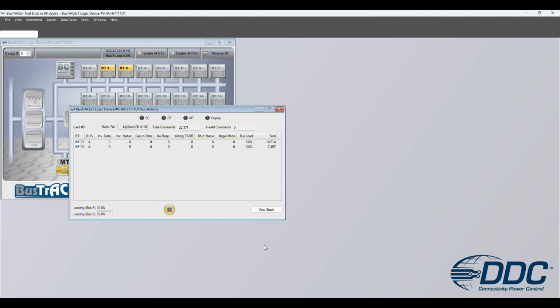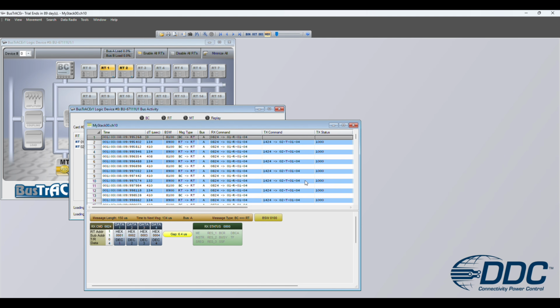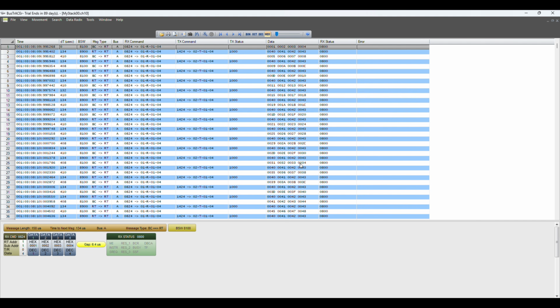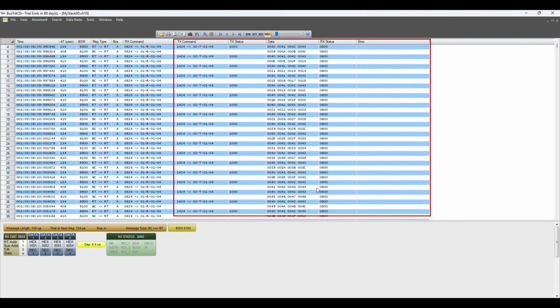The MIL-1553 adapter log shows the command word arriving with valid status words. No error bits, no no-response flag. The data count received at the MIL-1553 adapter confirms an exact match. Also, the adapter log confirms correct command sequence and interword gap timing, fully compliant RT to RT message structure verified by an off-the-shelf MIL-1553 device.